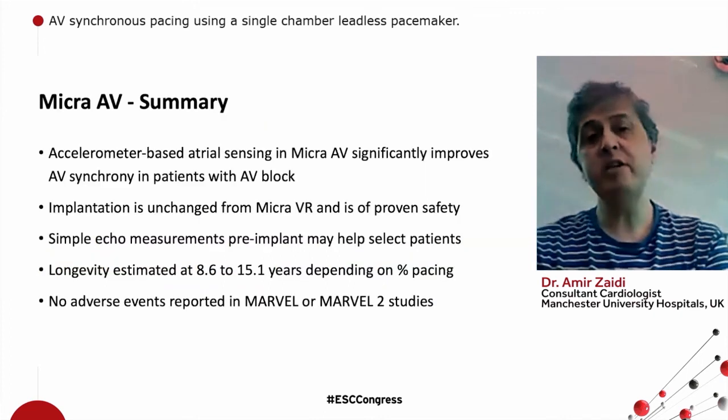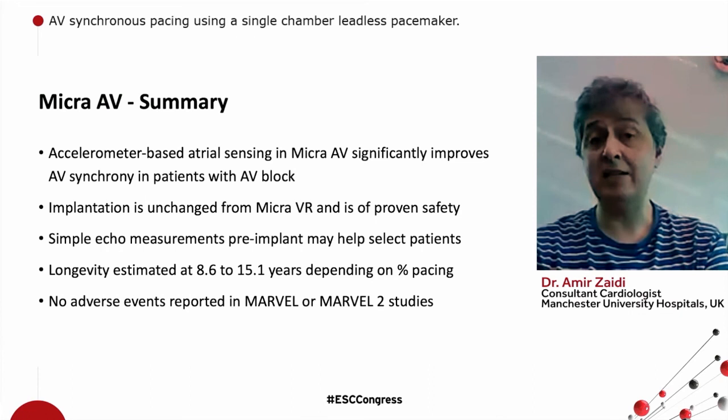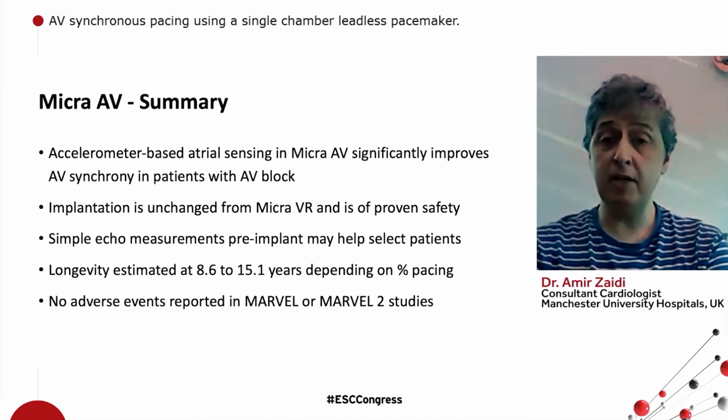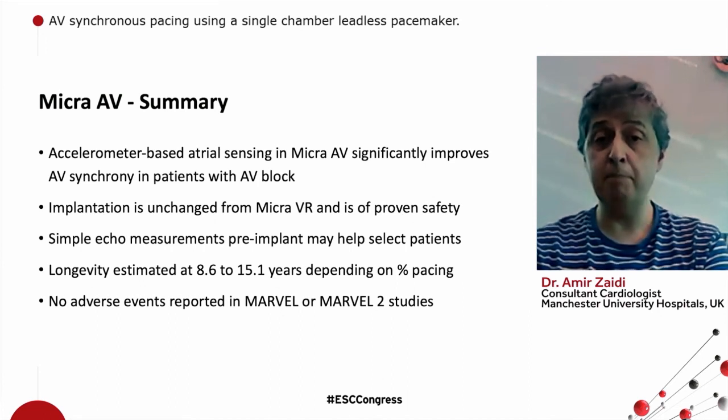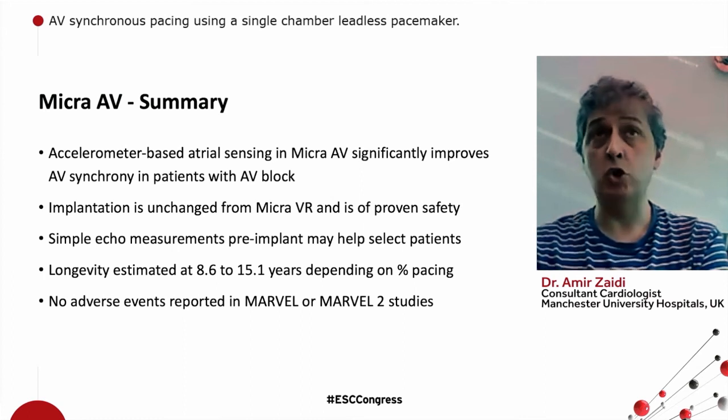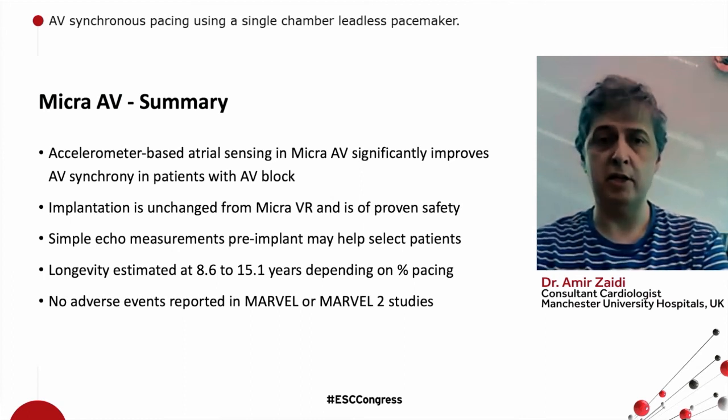So in summary, Micra AV provides accelerometer-based atrial sensing, which significantly improves AV synchrony in patients with AV block. It is not 100%, but it is over 90% in the vast majority of patients, and with appropriate rate support and mode switching, it will provide good long-term VDD pacing.